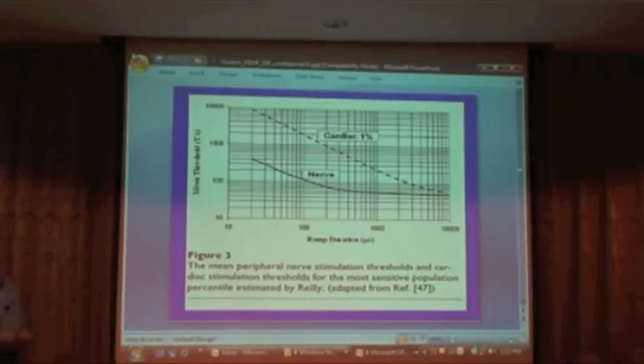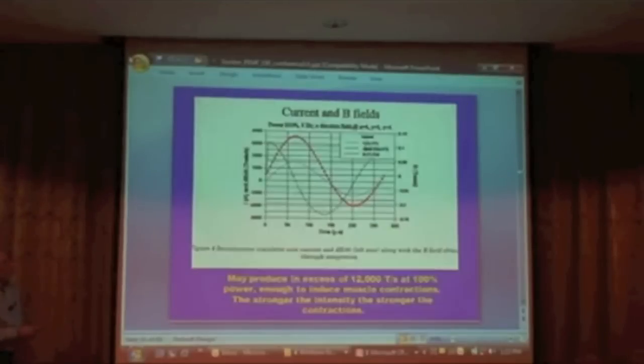Okay, this is the mean peripheral nerve stimulation thresholds and cardiac stimulation thresholds for the most sensitive population of tissues, basically. Again, you're talking in terms of Tesla per second. So you can see there are differences in terms of the density of the field and the ramp time of the pulse. So again, designing systems, depending on how long you apply the signal for, if it's short, they need to be much stronger. If it's longer, it could be a smaller signal, etc. But every tissue will have different current densities, or different densities in terms of how it accepts the signal.